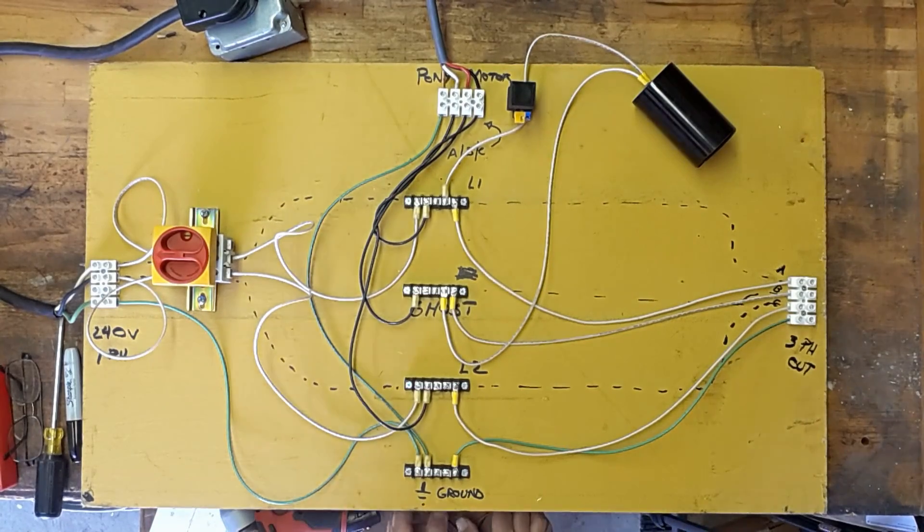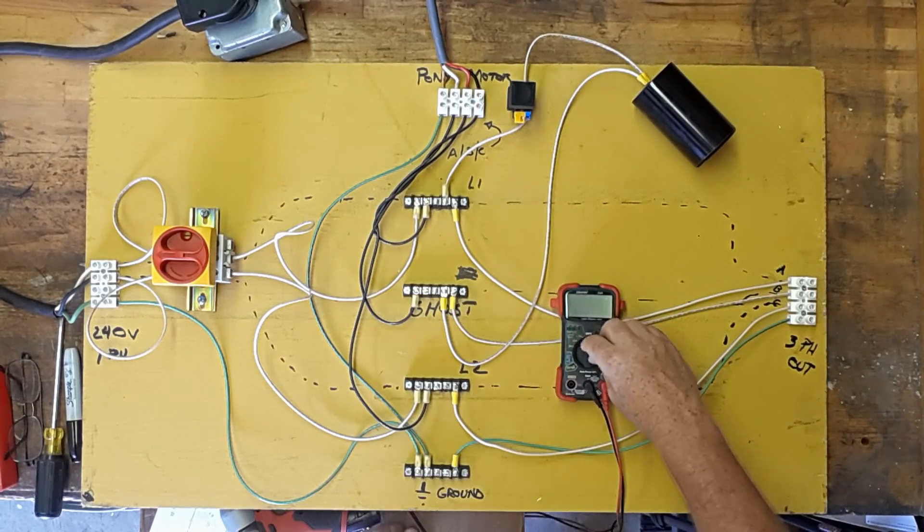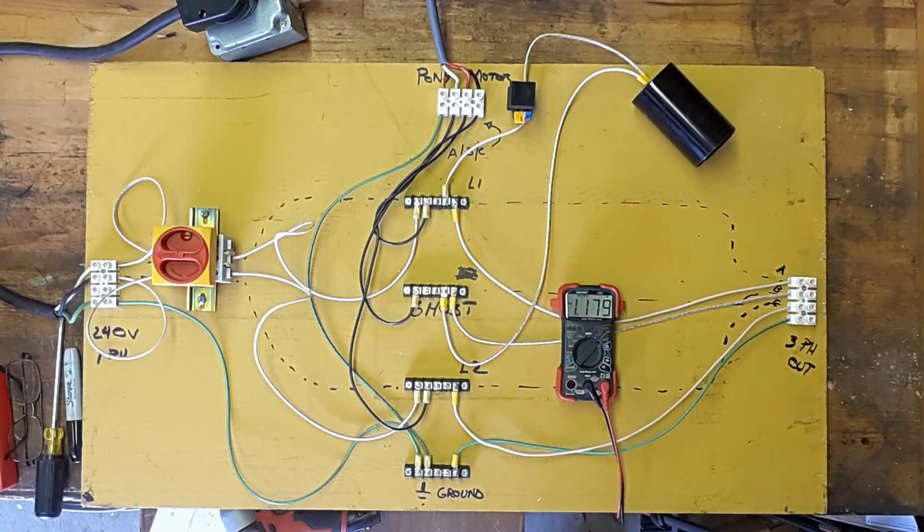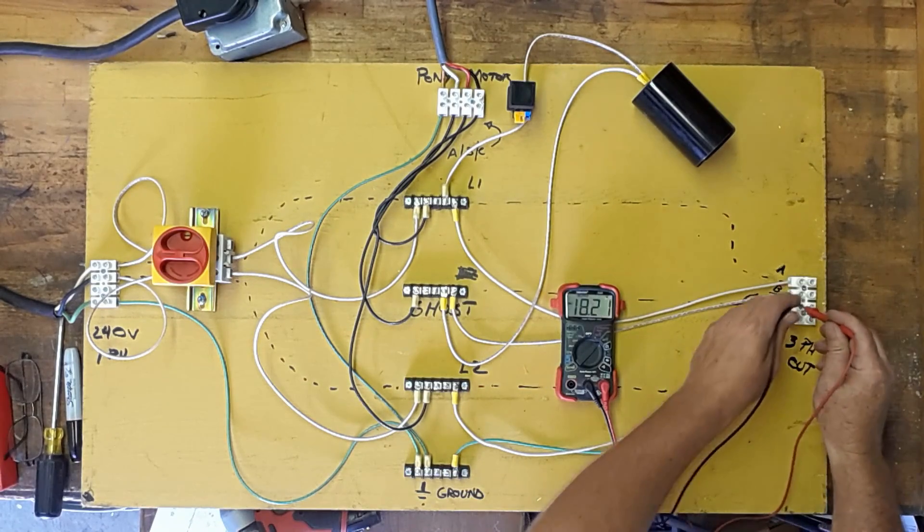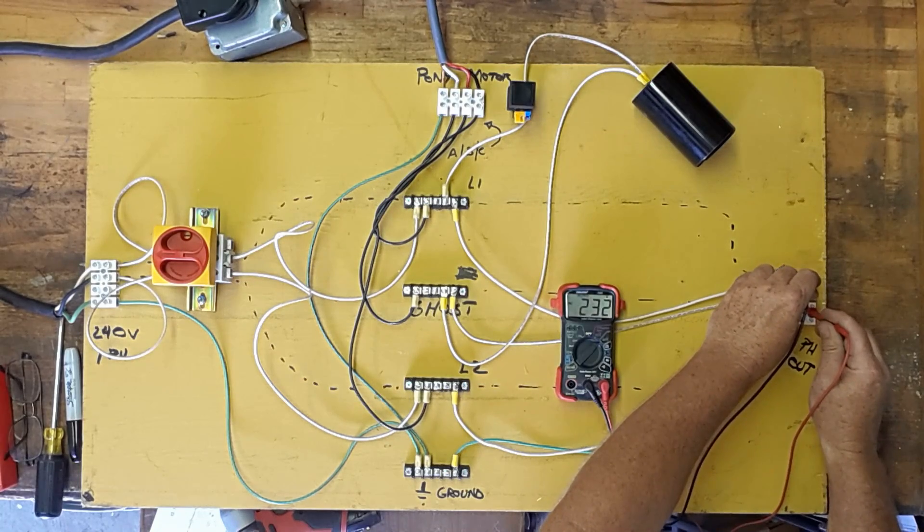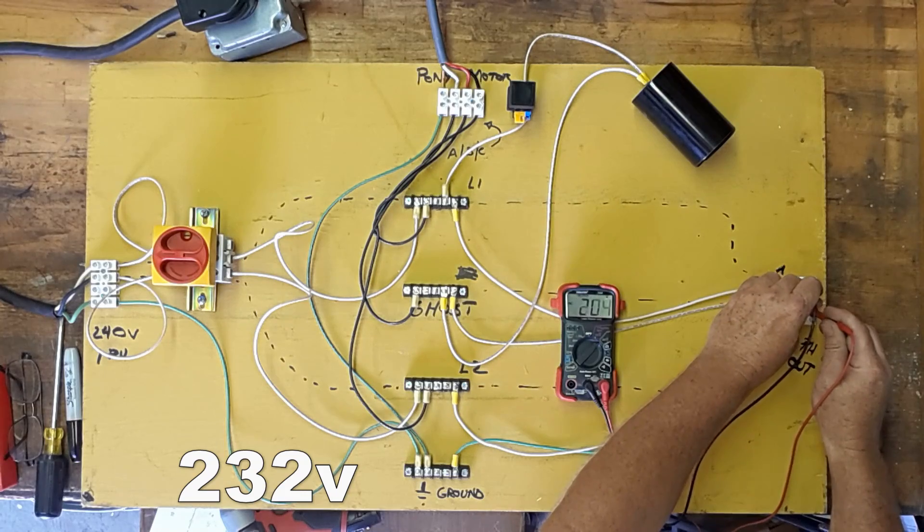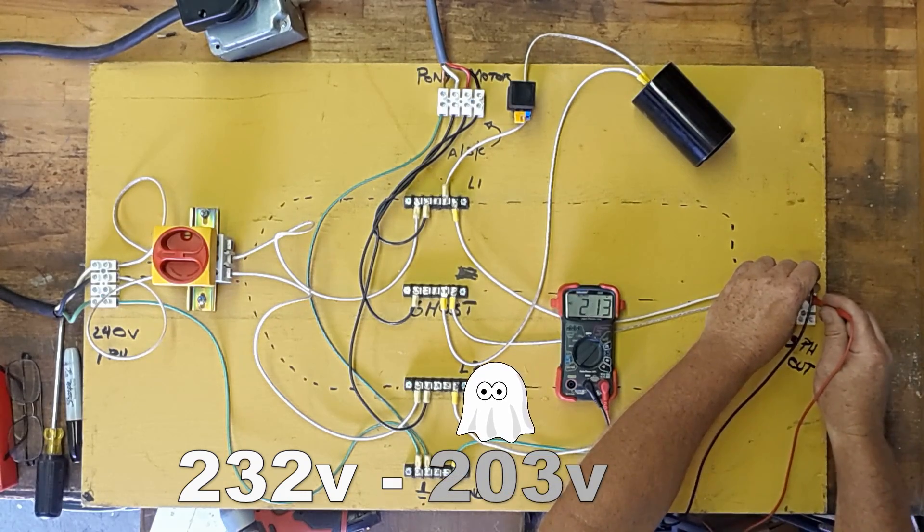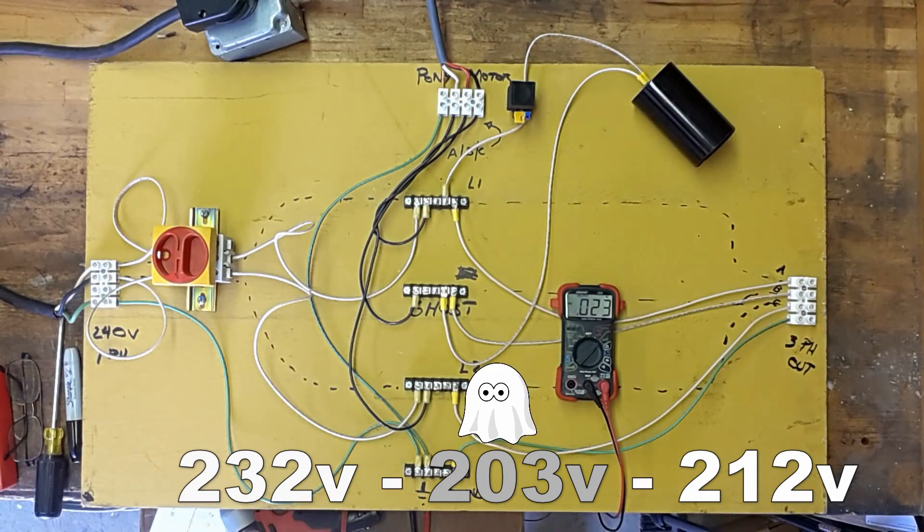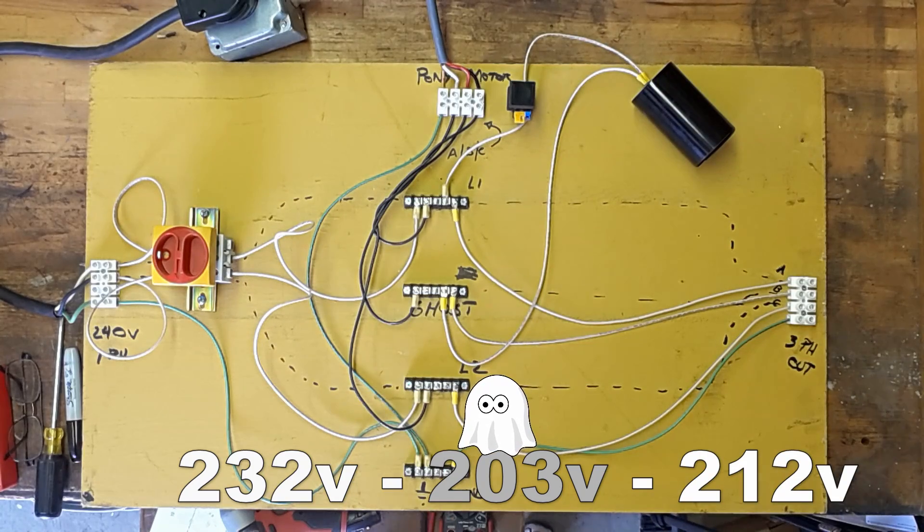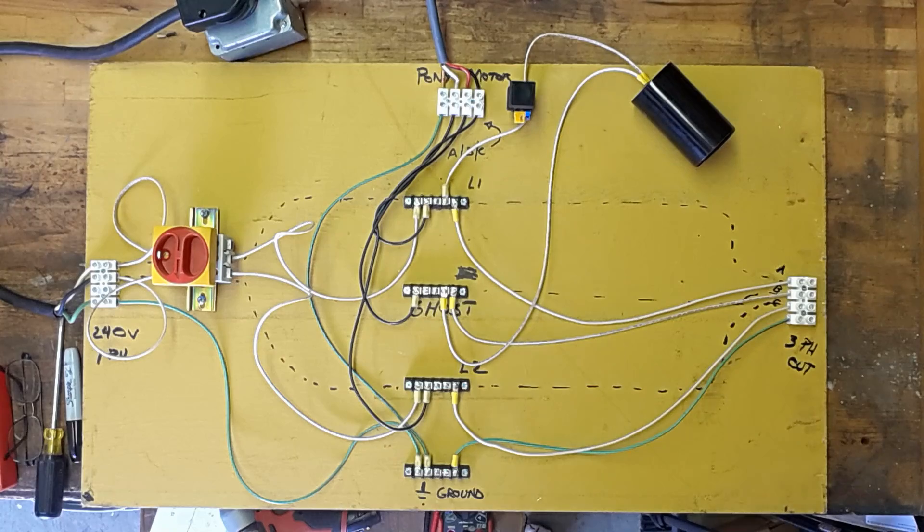There we go. Up and running. Now let's measure these three legs. We've got 232, 203, and 212. So you can see, the ghost leg was generating some power. But not a lot. And the voltages were way out of whack.